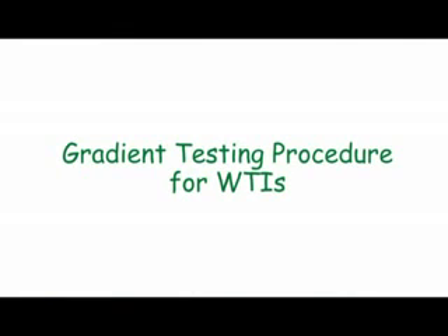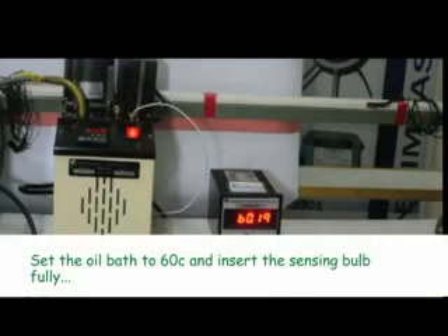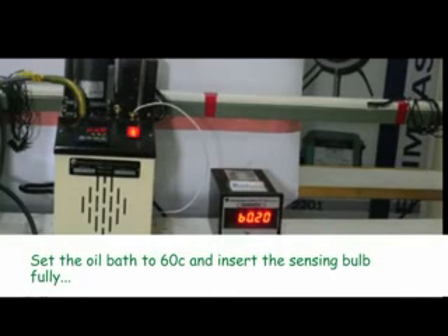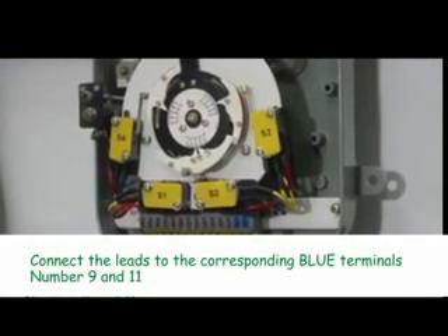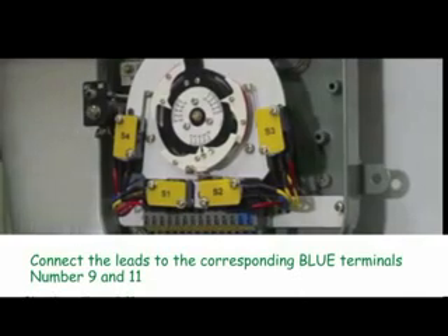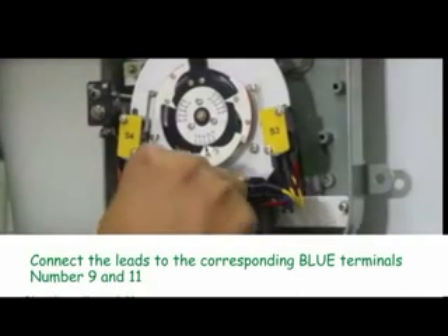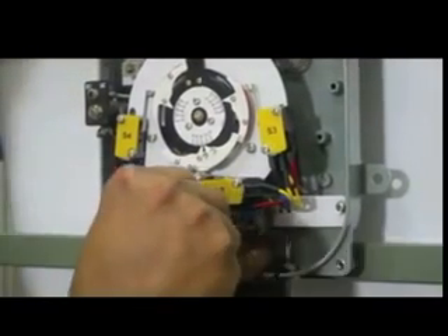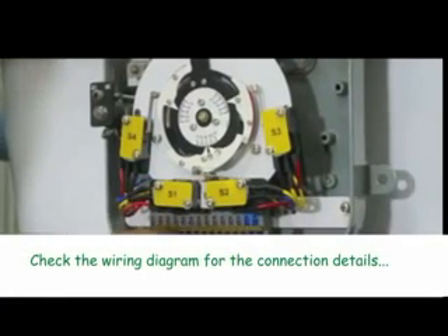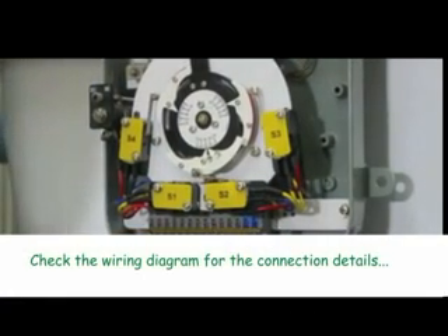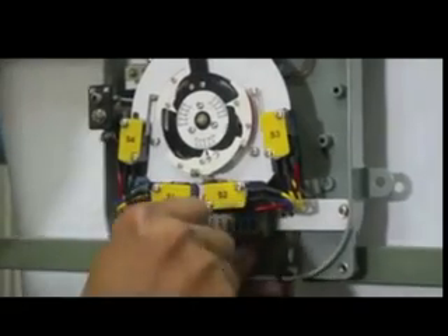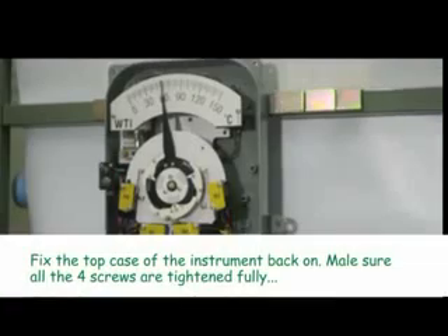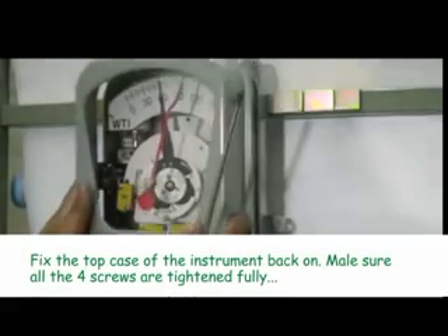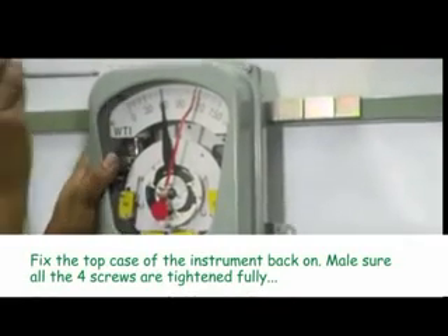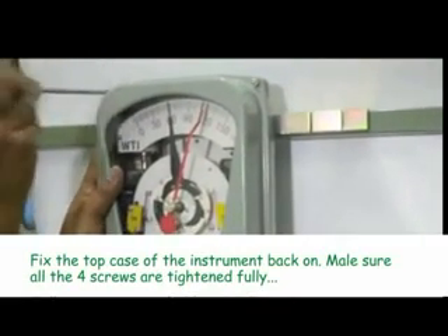Gradient testing procedure for WTIs. Set the oil bath to 60 centigrade and insert the sensing bulb fully. Connect the leads to the corresponding blue terminals number 9 and 11. Check the wiring diagram for the connection details. Fix the top case of the instrument back on. Make sure all the 4 screws are tightened fully.